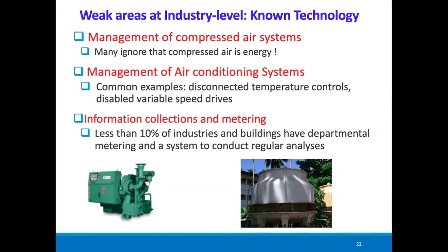Most importantly, information collection and metering. Less than 10% of industries, by our estimates, have separate metering in separate departments. For an office building, at least floor by floor metering, along with a system to collect energy use information and conduct regular analysis, is absent in most buildings and industries. These have to be set up for good monitoring of energy use.